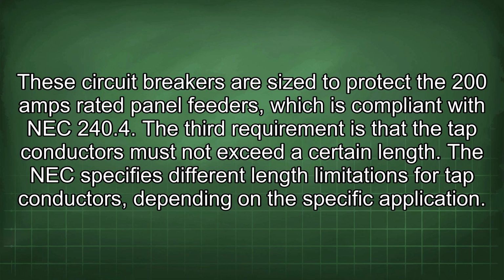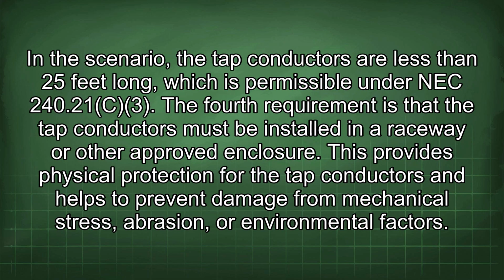These circuit breakers are sized to protect the 200 amp rated panel feeders, which is compliant with NEC 240.4. The third requirement is that the tap conductors must not exceed a certain length. The NEC specifies different length limitations for tap conductors, depending on the specific application. In this scenario, the tap conductors are less than 25 feet long, which is permissible under NEC 240.21(C)(3). The fourth requirement is that the tap conductors must be installed in a raceway or other approved enclosure.